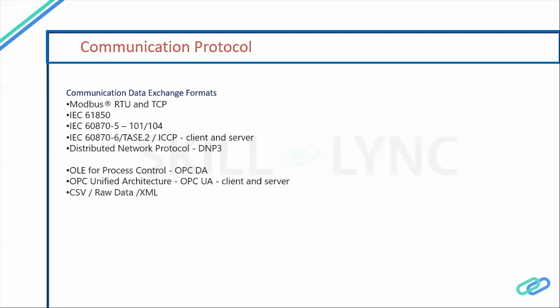IEC 61850 is basically for substation automation. In IEC 61850 data comes with a timestamp, giving a sequence of events. Any device trip or start or any unbalance is recorded with a timestamp. IEC 60870-5-101 and 104 are basically for SLDC communication purposes only. IEC 60870 is for client and server architecture.